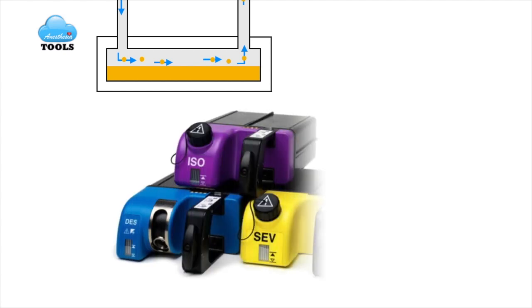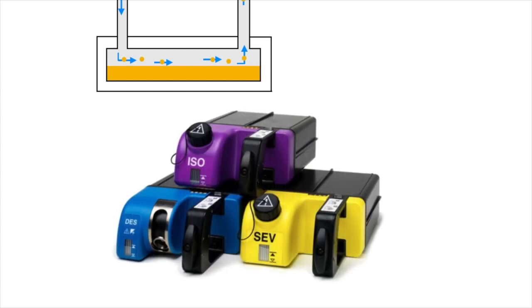The cassette is a leak-proof metal box which has a smaller front portion, color-coded to the specific agent, and a larger rear portion that is black in color. The front portion has an agent-specific filling system, a glass window to display the level of the anesthetic liquid, and a handle with a lever for locking the cassette in the slot provided on the anesthesia machine.